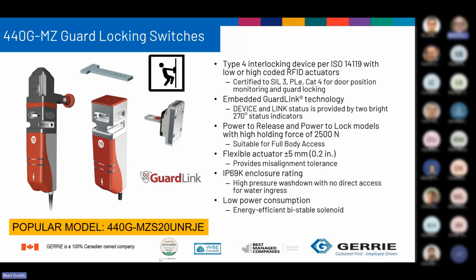One thing to note, though, is that once you teach these, I believe it's 4 or 8 times, they can only be taught, I believe, 8 times. Once you exceed the number of teaches, the switch becomes a doorstop because basically it means that someone's been defeating this thing. So again, a guy comes in on the Friday night, bypasses the door, puts the actuator back on Sunday night, whenever he's done his shift, and then he does that for a few weeks, and then all of a sudden it's like, hey, the switch doesn't work anymore. And again, it does go into a lockout state that is non-recoverable. So again, they do have their place, but you need to know when and where.